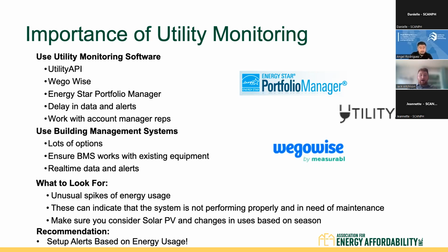And then you have what to look for. Unusual spikes. These can indicate the system is not performing properly and is in need of maintenance. Make sure you consider solar PV changes in use based on the seasons. So you want to make sure you're not setting up alerts that are going to falsely alert because it's winter and you have less solar production, and that's why you're seeing an uptick in kilowatt hour usage. Next slide, please.